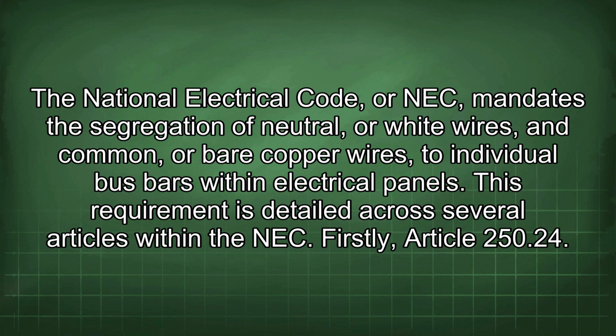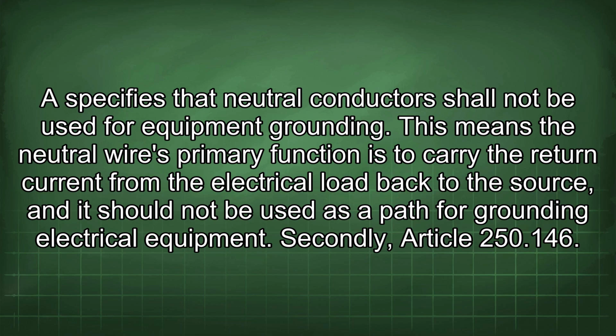Firstly, Article 250.24(A) specifies that neutral conductors shall not be used for equipment grounding. This means the neutral wire's primary function is to carry the return current from the electrical load back to the source, and it should not be used as a path for grounding electrical equipment.